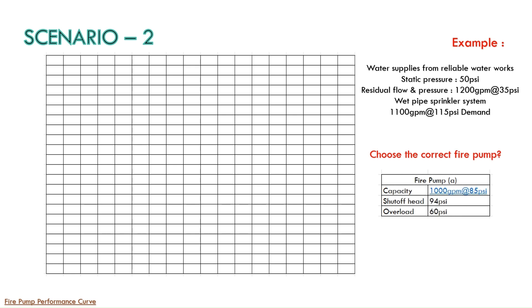First option is 1000 GPM at 85 PSI with shutoff at 94 PSI and overload 60 PSI. And option B the fire pump capacity is 750 GPM at 95 PSI shutoff at 98 PSI overload 76 PSI.